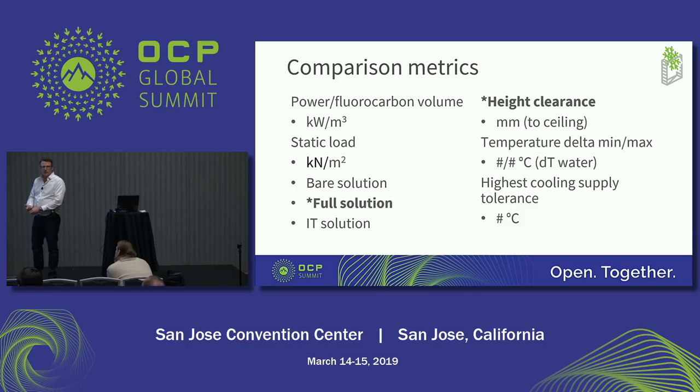But what is the tolerance? So can you tolerate a delta that is lower than 4 degrees Celsius? Now, in our case, no, because then the flow rates get so high that we can't manage the safety system anymore. The lowest temperature delta requires very high flow rates, especially with the higher energy tolerances. Those heat exchangers are going to wear internally. Beyond 14 degrees Celsius, the flow rate gets so low that we can't measure the flow anymore, especially with the lower energy input. That is an example of how that becomes relevant.